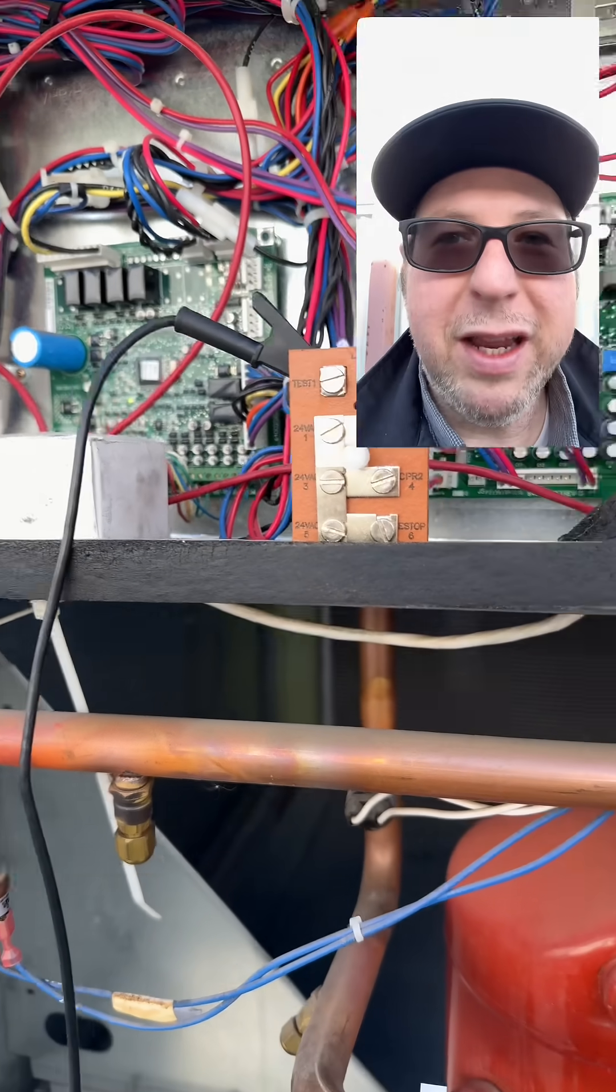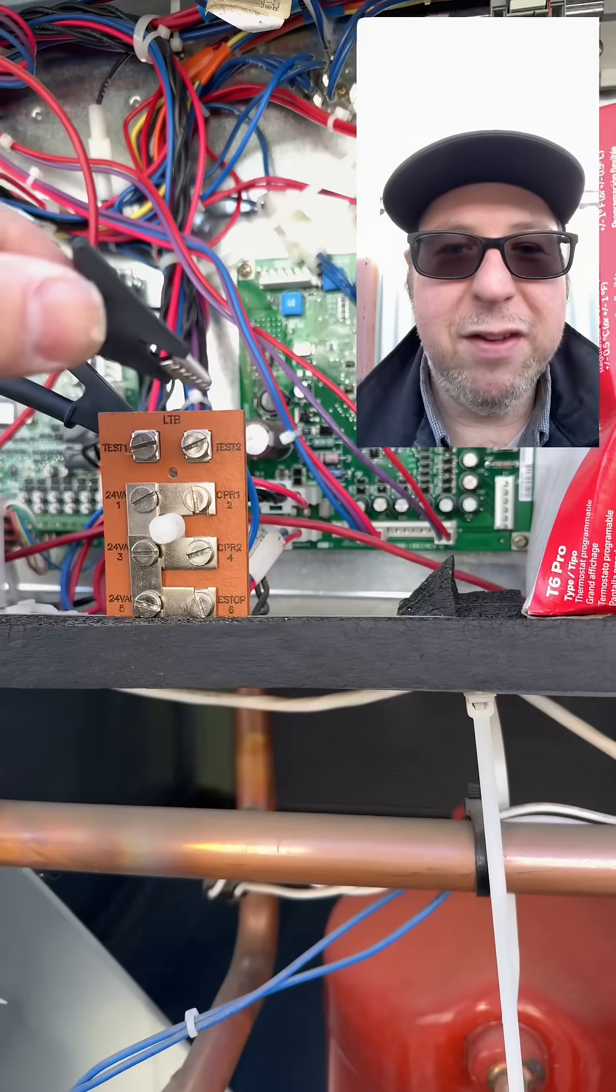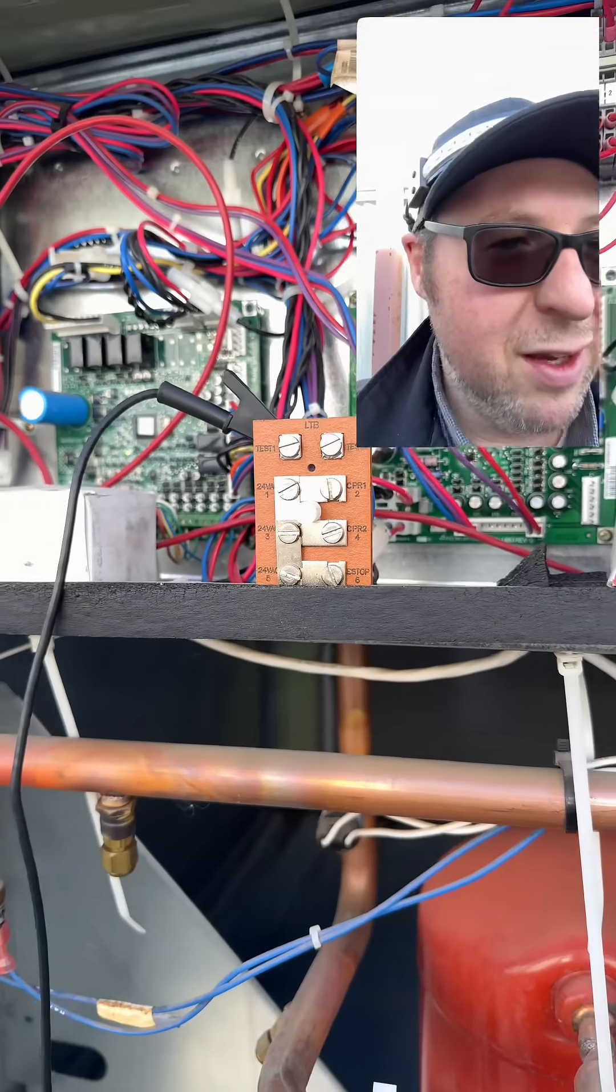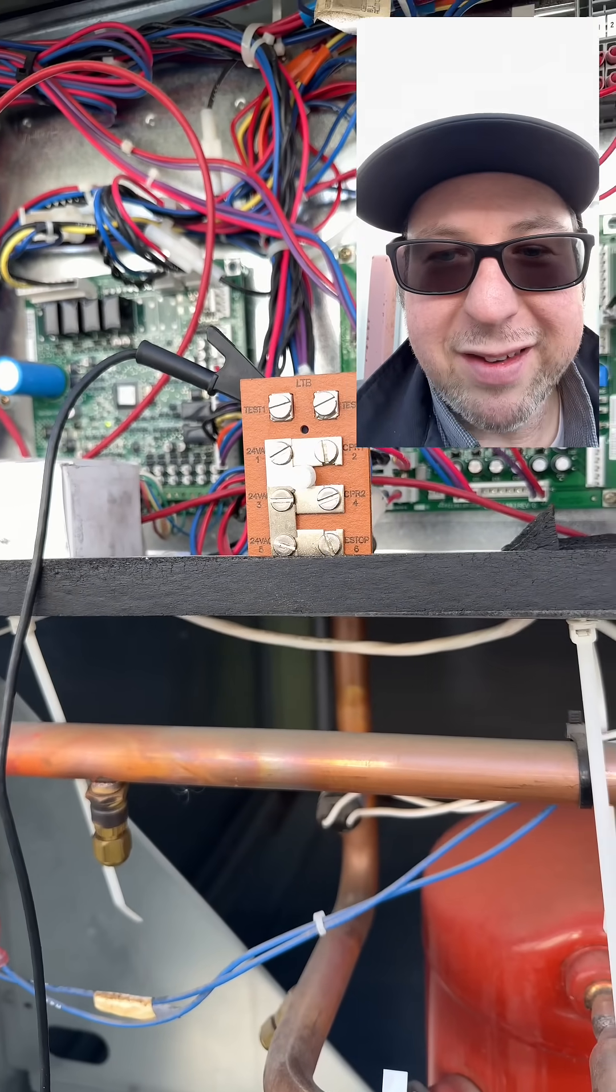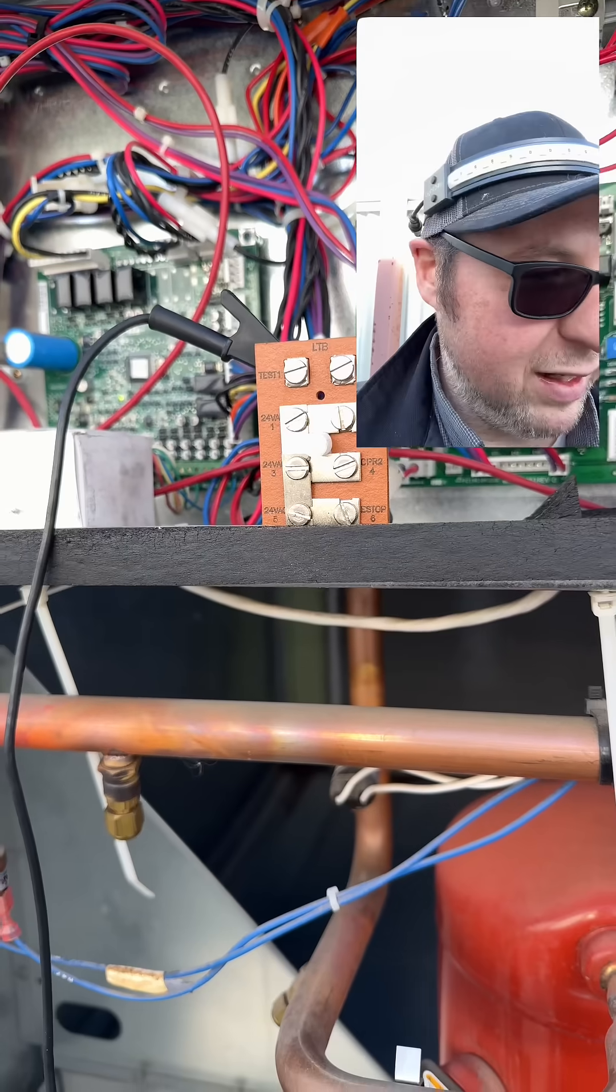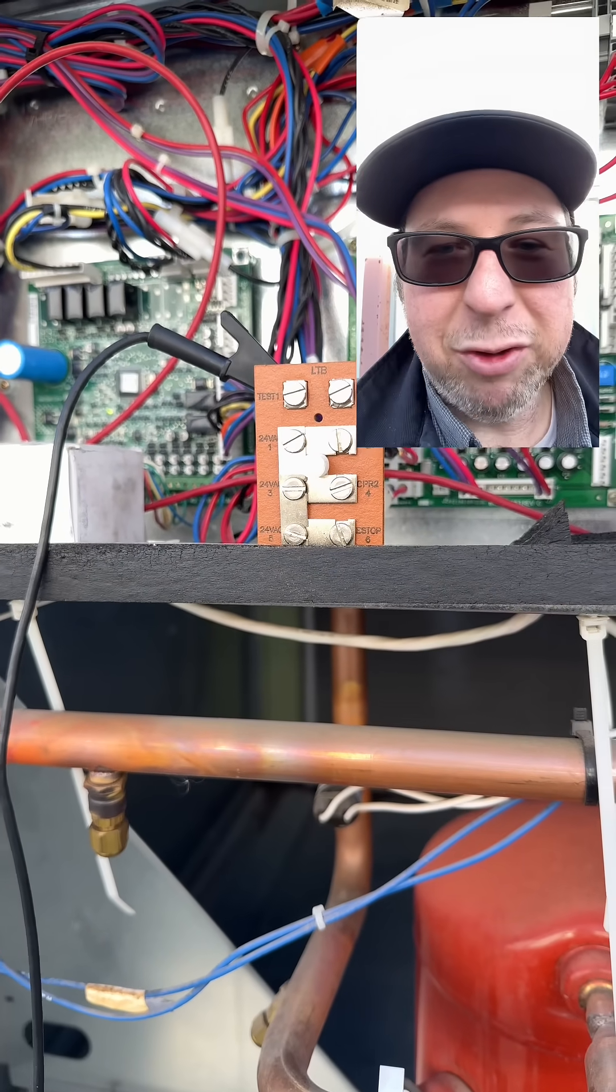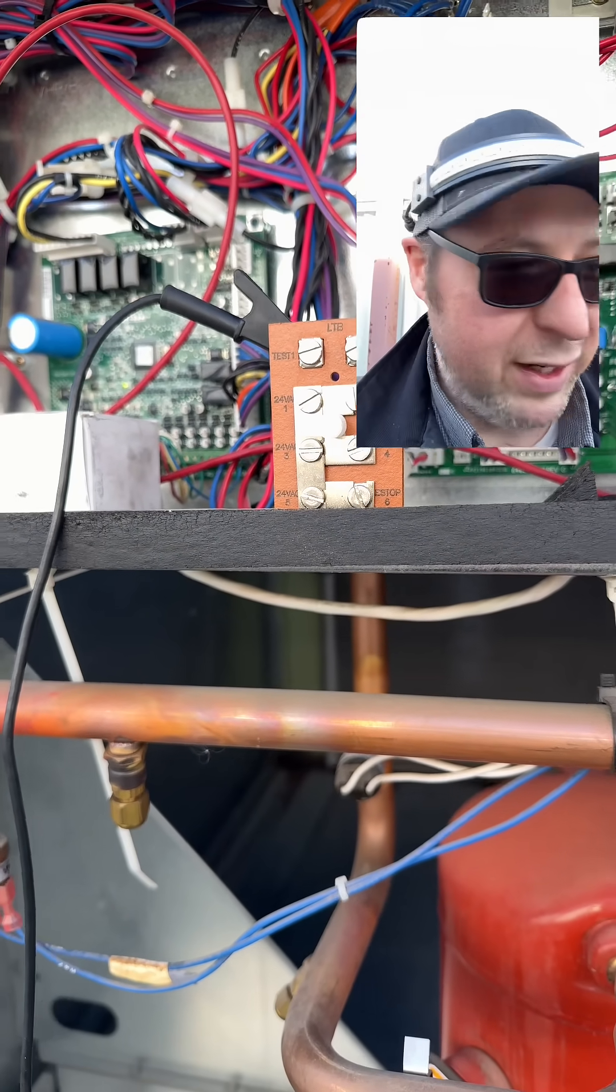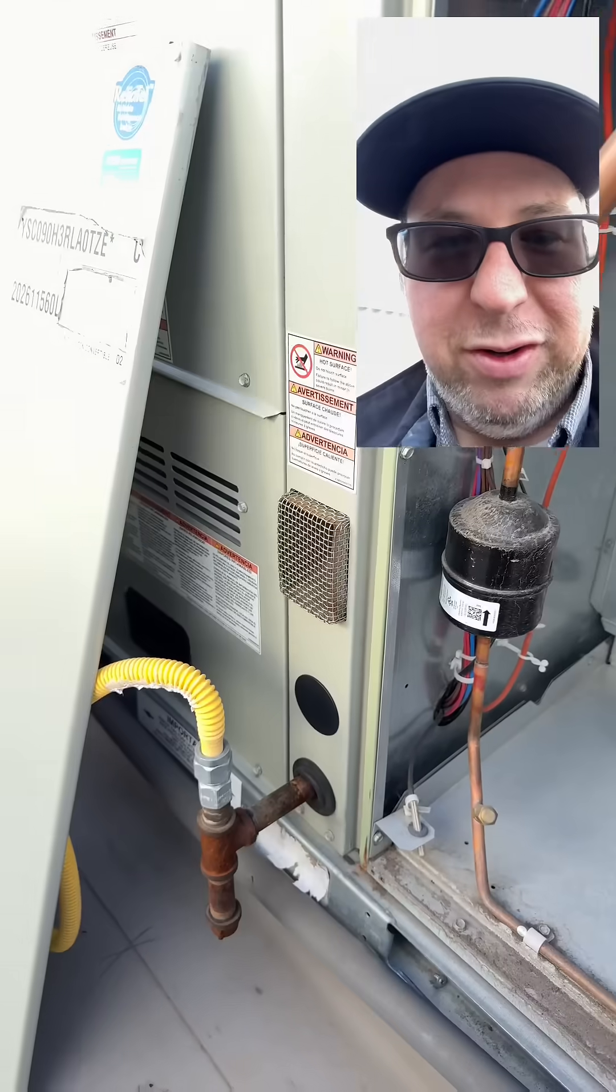There's my heater. Now like I said, if you just leave this on here it'll cycle through everything in that order, but it's like for 10 seconds or something like that. So when you're trying to diagnose it, it's too quick. I want to make sure this heater turns on.